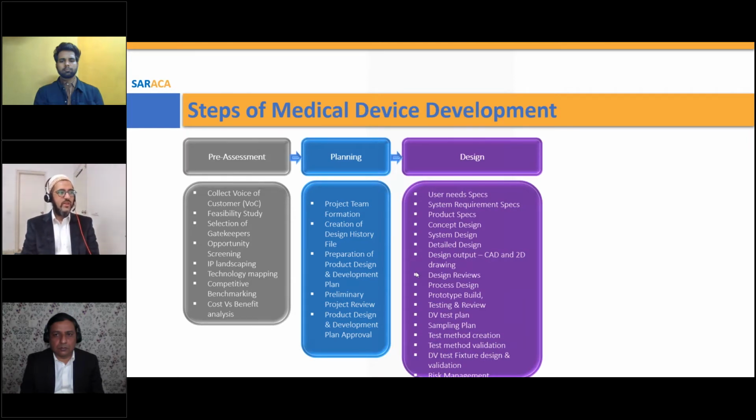So in this, like I earlier said, you'll formulate your user needs spec. You will list down all the specifications which go into user needs. So user needs are again divided into functional needs or performance needs, and then regulatory, ergonomics, usability needs, packaging, labeling, supply chain, reliability, serviceability. So all this will be part of the user need requirement. And similarly, if it's a big system, then it's sometimes called system requirement specification.